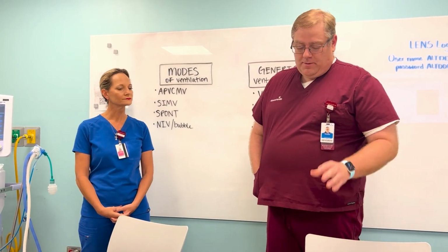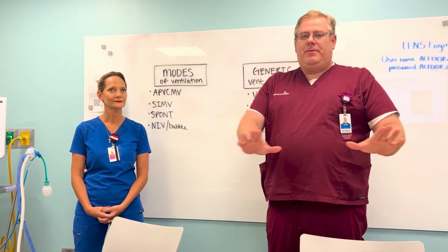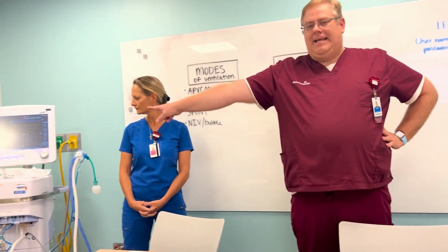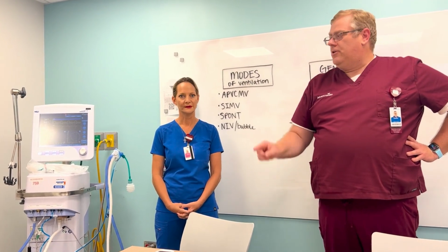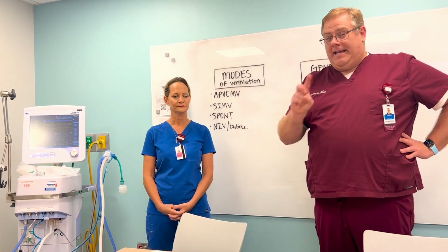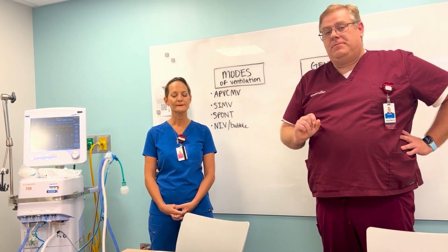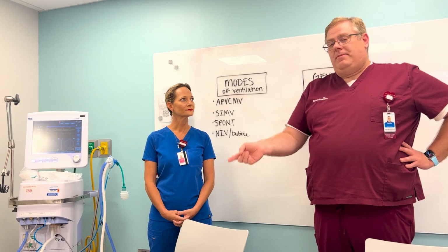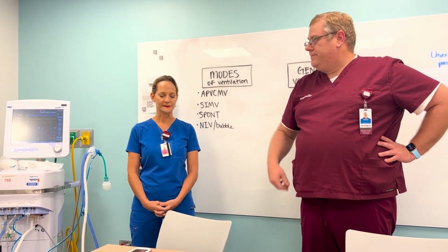So that is one of the main things, but the biggest thing that I want to make sure absolutely everybody is aware of is when you hit that silence button, you never walk out of the room with the silence button still on. It takes 2 minutes for the silence button to go away. You either stay in the room for 2 minutes or hit it a second time, so that the alarms are reset. Because if something happens to that baby within that minute that you walked out of that room, it's really our responsibility.